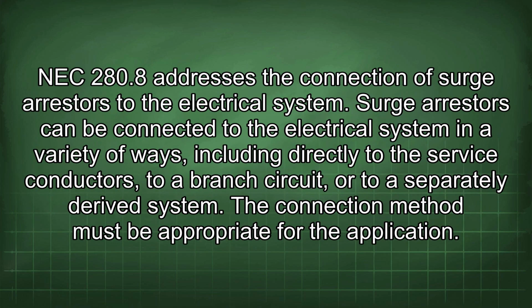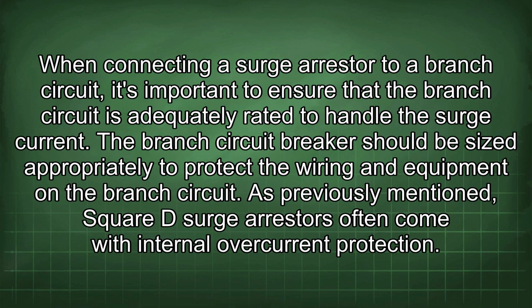NEC 280.8 addresses the connection of surge arrestors to the electrical system. Surge arrestors can be connected to the electrical system in a variety of ways, including directly to the service conductors, to a branch circuit, or to a separately derived system. The connection method must be appropriate for the application. When connecting a surge arrestor to a branch circuit, it's important to ensure that the branch circuit is adequately rated to handle the surge current. The branch circuit breaker should be sized appropriately to protect the wiring and equipment on the branch circuit.